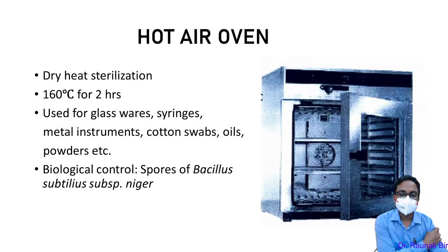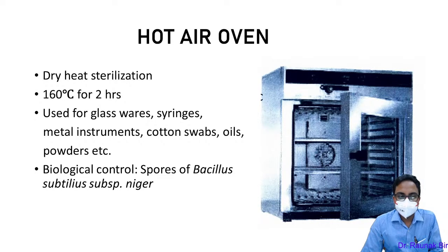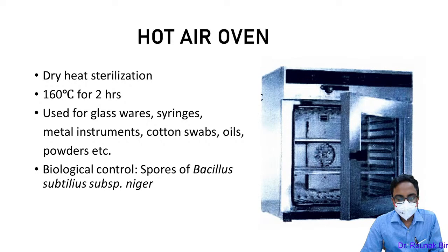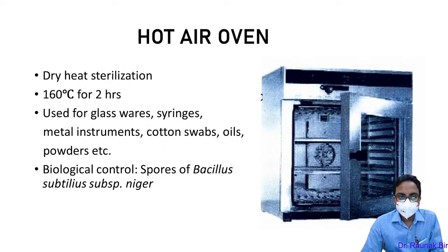Coming firstly to the hot air oven: it is a dry heat sterilization method. We keep the articles and heat at 160°C for two hours. Articles sterilized by this process include glassware, glass syringes, metal instruments, sharp metal instruments, cotton swabs, and all types of oils such as glycerin and paraffin, and powders like the dusting powder used for gloves.